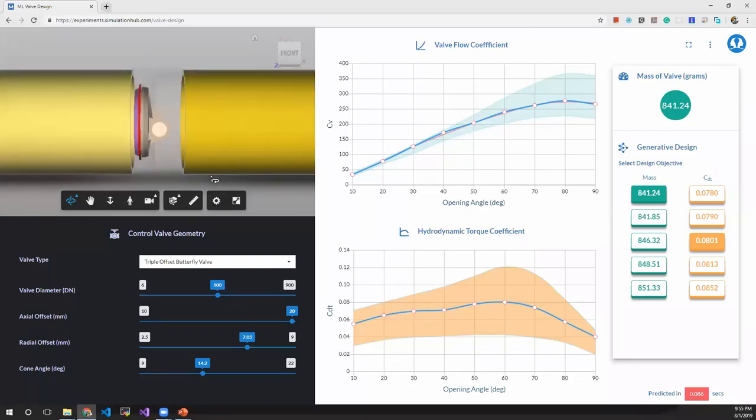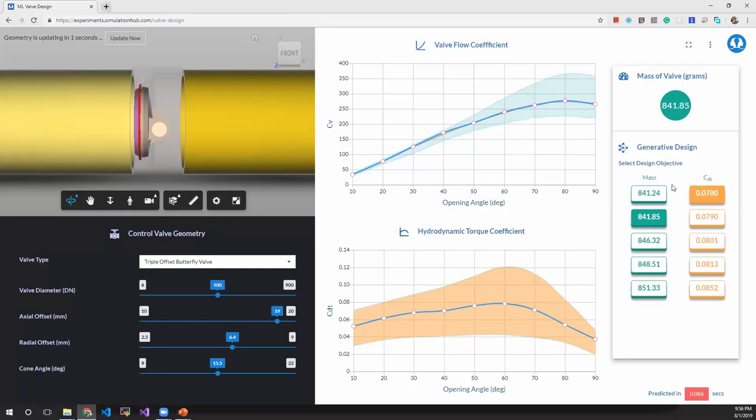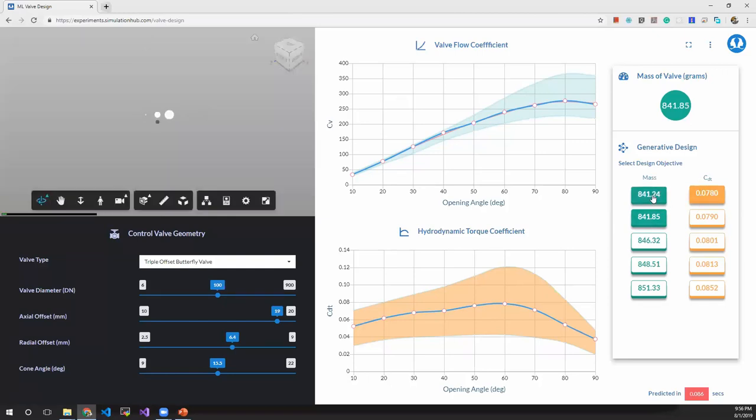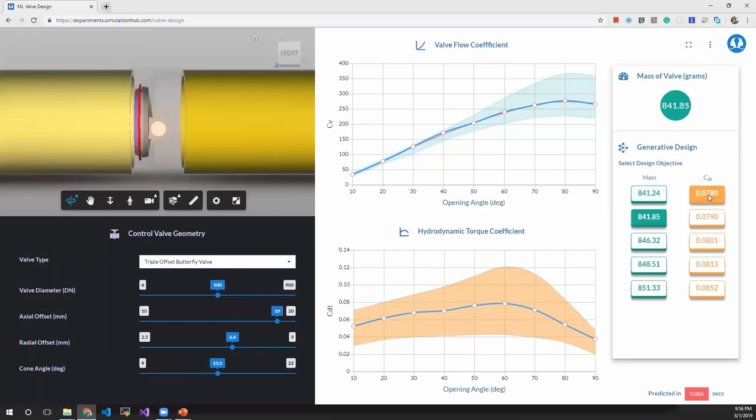Now, what is the point about multiple objective criteria? Here, we gave five different design options to the user where they are ordered in ascending order of mass, that is the weight of the valve, or in terms of hydrodynamic torque coefficient. When I select the lowest mass design, then the hydrodynamic torque coefficient increases. If I go for a lower hydrodynamic torque coefficient, then the mass increases a bit. But this seems to be a better design overall compared to the lowest mass one. So I would rather prefer to go with this design.